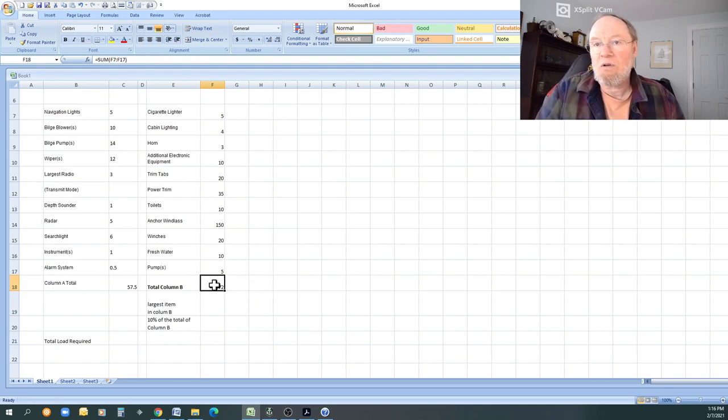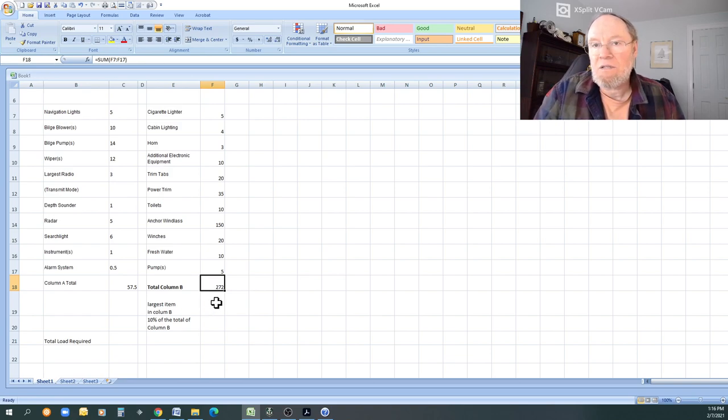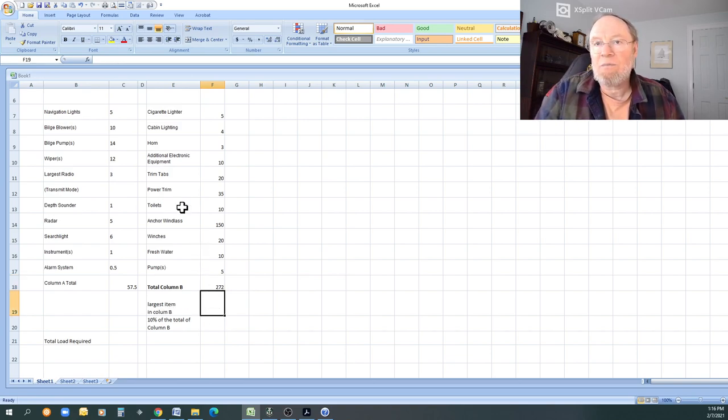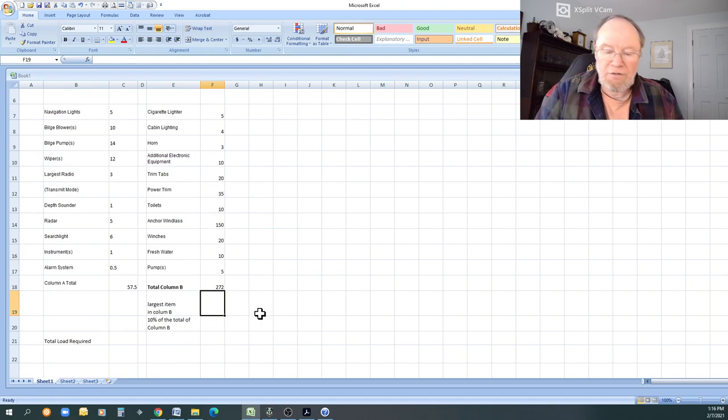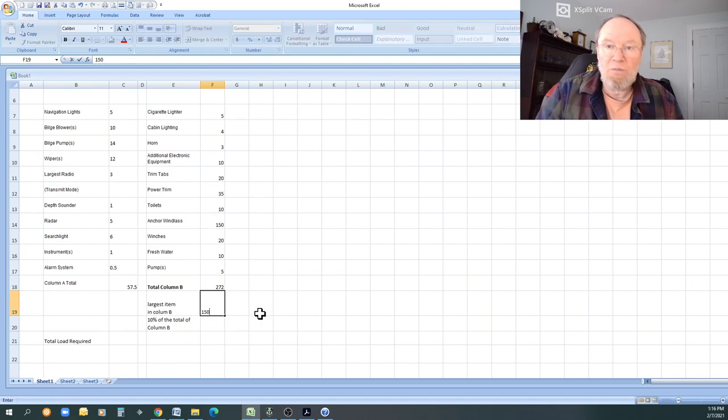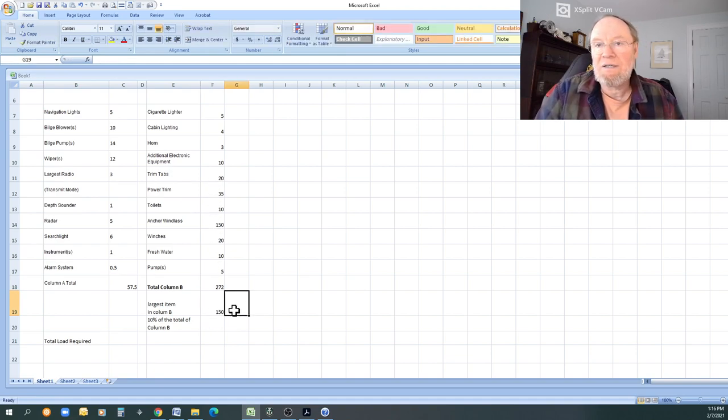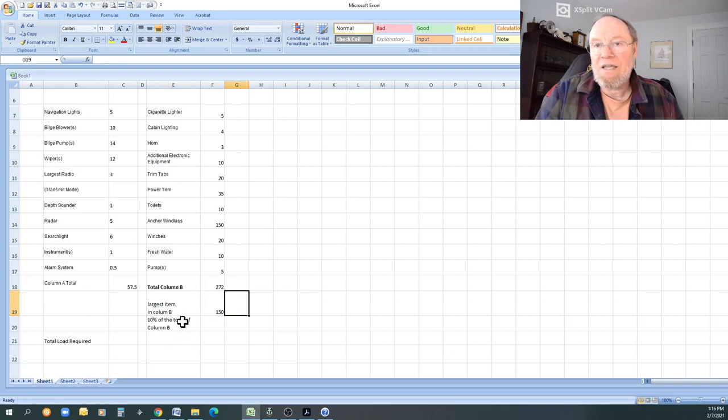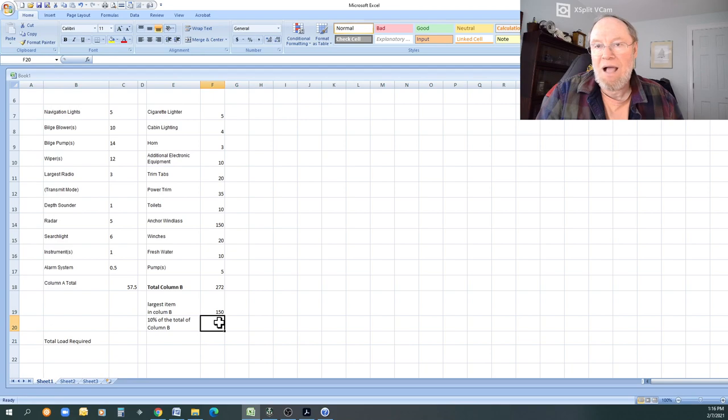What are you going to do to get out of it? So there's the total, 272 amps. That's going to be the total current in that. Now, here's the magic. The largest item of column B, you have to look. That's 150. That's easy. I'm going to put in 150. Now, what is 10 percent of the total? Real easy.